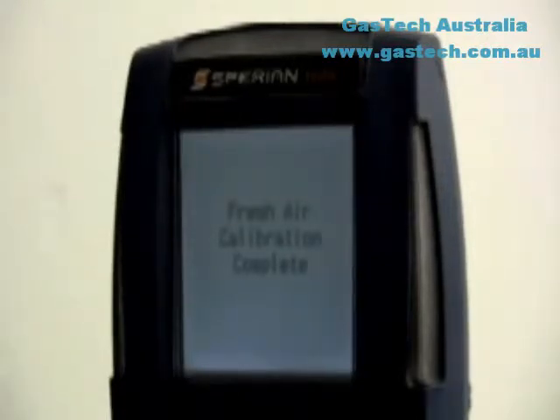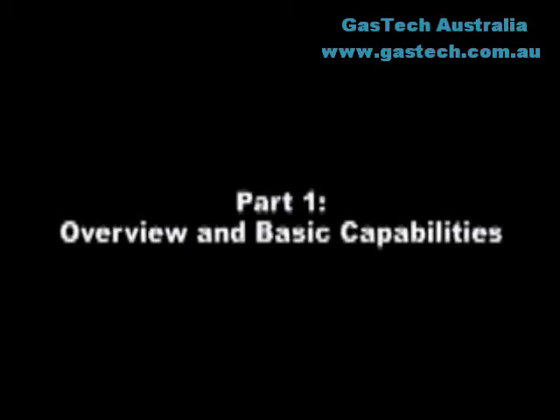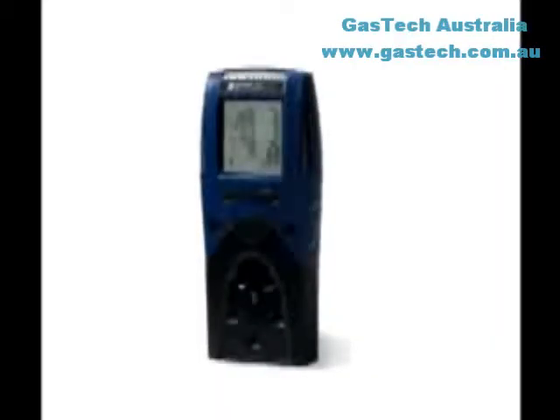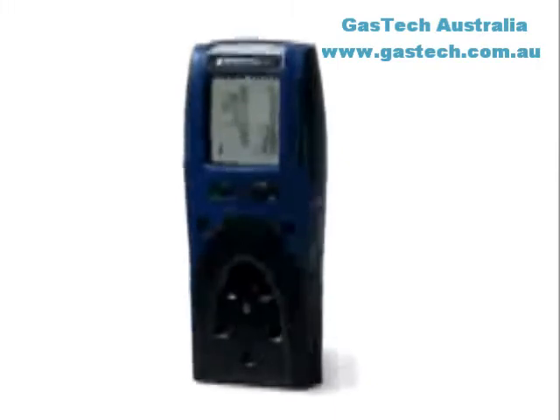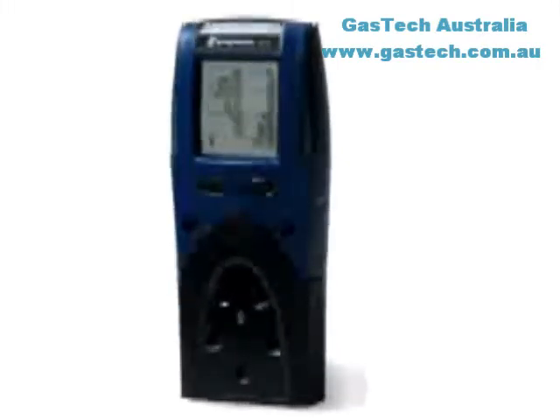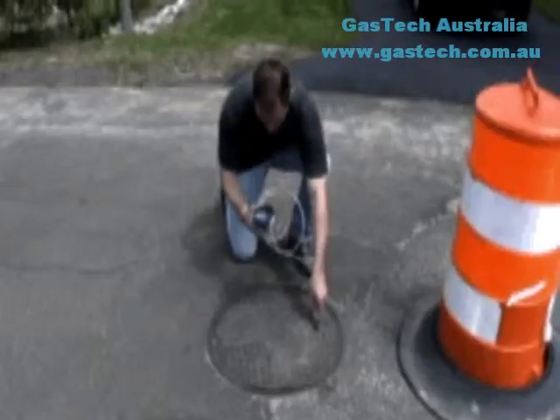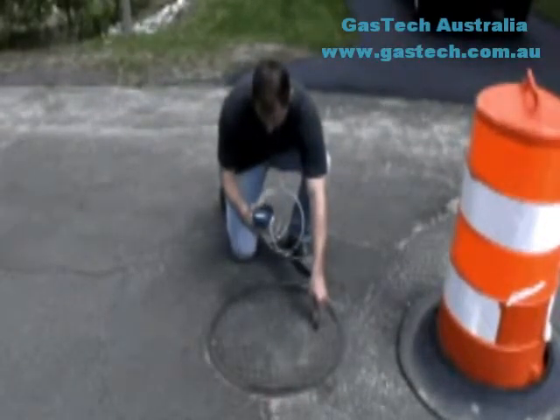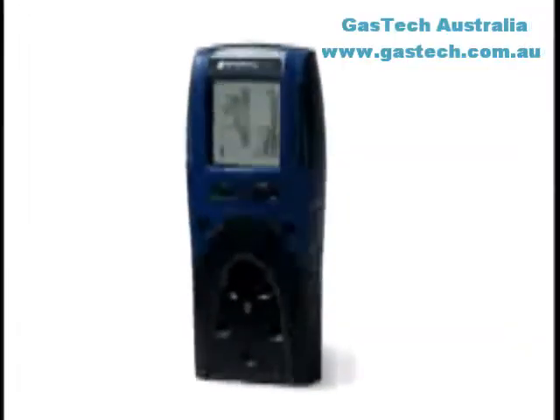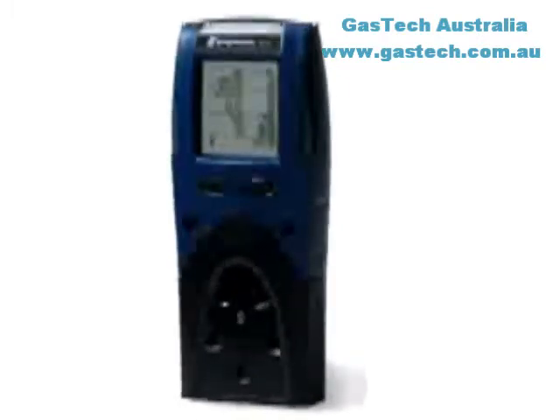The instrument will automatically adjust the oxygen, combustible gas, and toxic gas readings to match the concentrations expected in a fresh air environment: 20.9% oxygen, 0% LEL for combustible gas, and 0 parts per million for all toxic gases except CO2. Once the fresh air calibration has been successfully completed, the PHD6 will automatically proceed to the automatic span calibration sequence and begin another 5-second countdown. Press the mode button before the end of the 5-second countdown to initiate the span calibration adjustment.